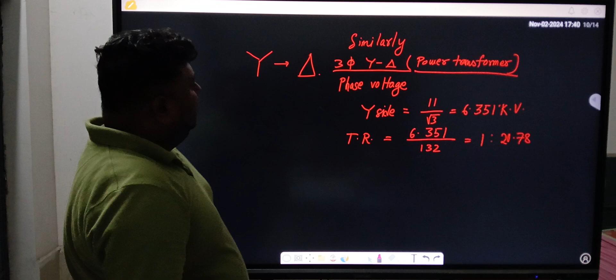Here the same phase voltage we have to check for star side first. Why star side? Because we have to get the exact value, because in star only our utilization is there. Whatever we are getting in neutral is in star, not in delta. We are not getting any neutral in delta. So it is essential that the turn ratio should be exact in star. So here also we are checking star side the same. We are doing 11 by root 3. We will be getting 6.351 kV. Then the turn ratio will be, as I have told, always divided by the higher voltage.